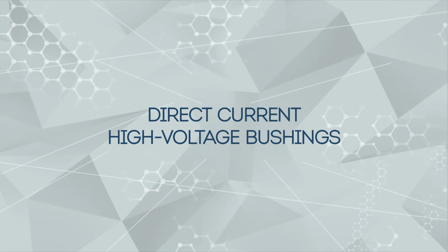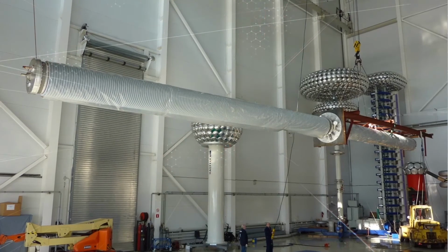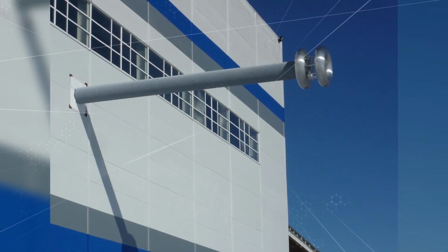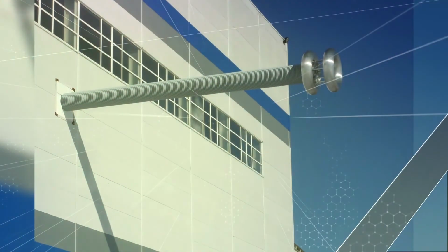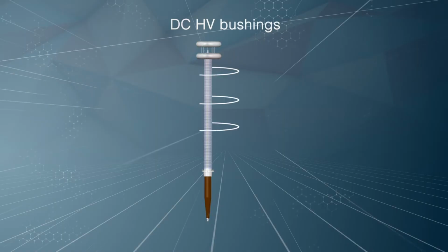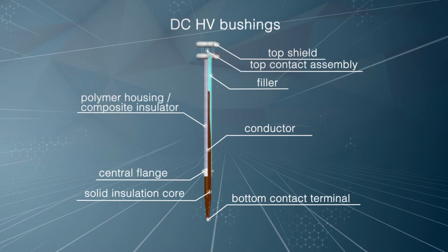Direct current, high voltage bushings, intended for installation on equipment, which can operate on alternating and direct currents as well as their combination. Direct current bushings are installed on transformers specifically at a nearly horizontal angle, making it irrational to use bushings with porcelain housing. Besides, special fire safety requirements are applied to the bushings of this type, eliminating transformer oil as a possible filler. So modern DC bushings have solid insulation, polymer housing, and dry filler.